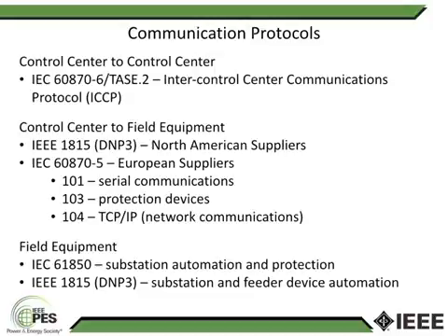At the top, for control center to control center communication, there's one worldwide standard for how utilities exchange information with other utilities, or how different SCADA systems within a utility exchange information with each other. It's called ICCP, an IEC 870-6 standard, meaning Inter-Control Center Communications Protocol.